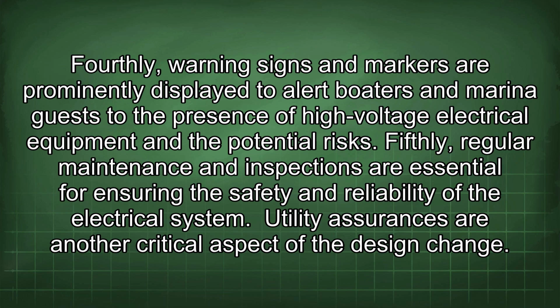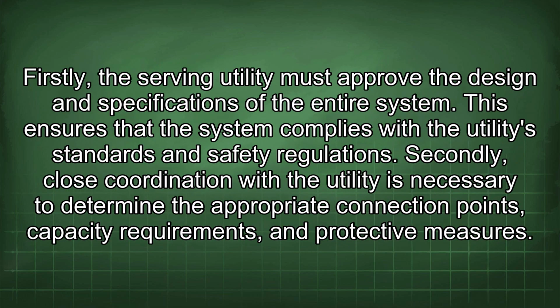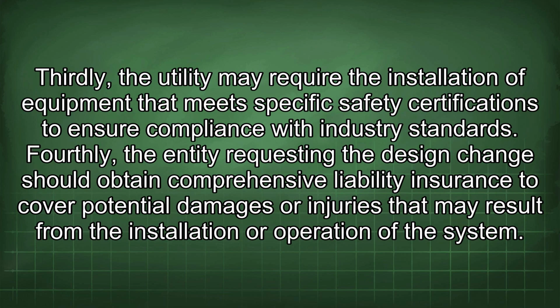Utility assurances are another critical aspect of the design change. Firstly, the serving utility must approve the design and specifications of the entire system. This ensures that the system complies with the utility's standards and safety regulations. Secondly, close coordination with the utility is necessary to determine the appropriate connection points, capacity requirements, and protective measures. Thirdly, the utility may require the installation of equipment that meets specific safety certifications to ensure compliance with industry standards. Fourthly, the entity requesting the design change should obtain comprehensive liability insurance to cover potential damages or injuries that may result from the installation or operation of the system.